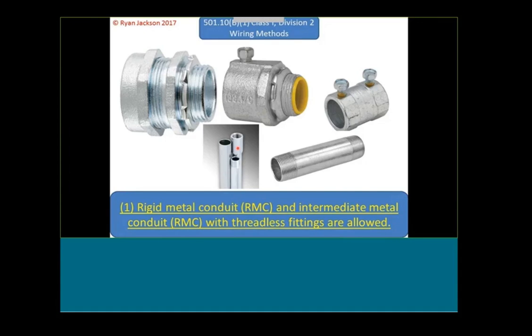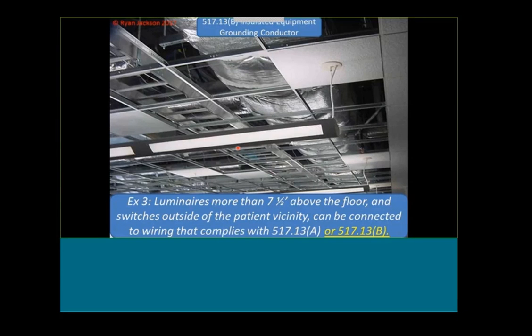Some of you guys might do a lot of healthcare, maybe hospitals, maybe you work at a hospital as maintenance staff. There's a really obscure rule that's been in the code for the last 30 years that says when you're above the ceiling of a patient care area, you still have to use special wiring. The lights in a patient care area have to be fed by special cables. Some of you might be shaking your head, trust me, you almost have to read it with a magnifying glass. 517.13B, it used to be exception 2, now it's exception 3, did require a special wiring method. It doesn't anymore in the 2017 code.